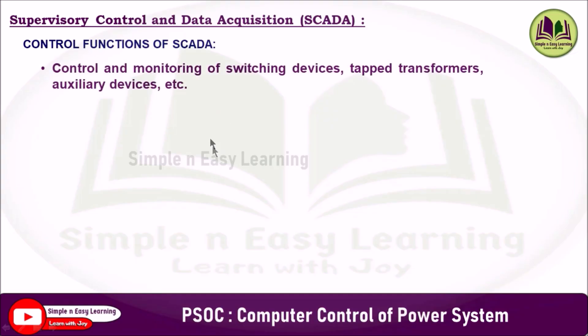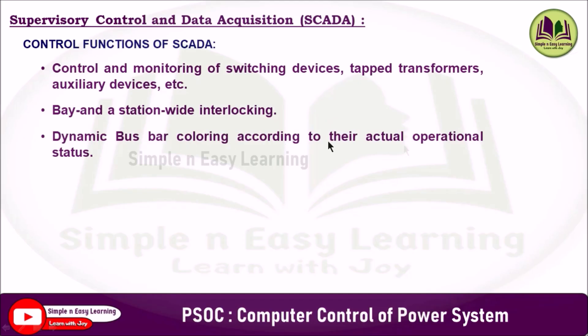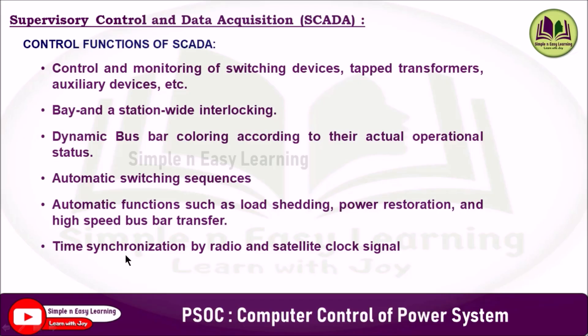The control functions of SCADA include control and monitoring of switching devices, tapped transformers, and auxiliary devices, as well as bay and station-wide interlocking. A single bay or a complete substation interlocking can be controlled using SCADA. Other control functions include dynamic bus bar coloring according to actual operational status, automatic switching sequences, automatic functions such as load shedding, power restoration and high-speed bus bar transfer, and time synchronization by radio and satellite clock signal.